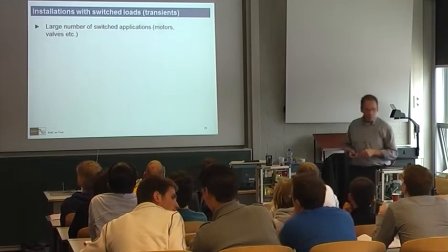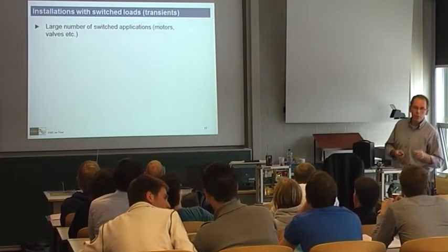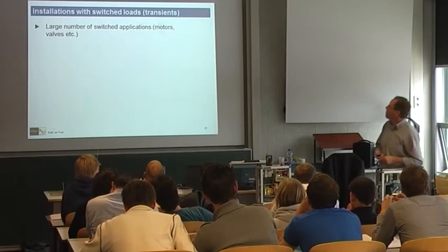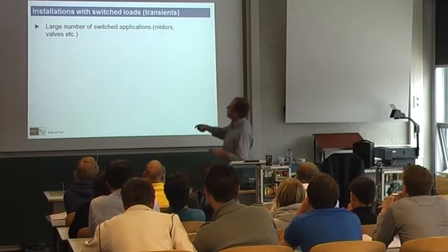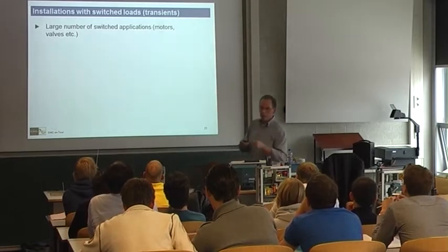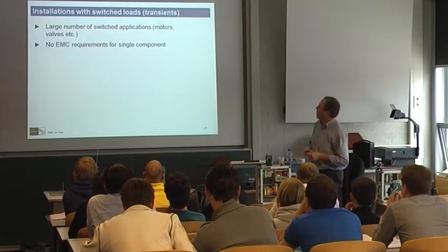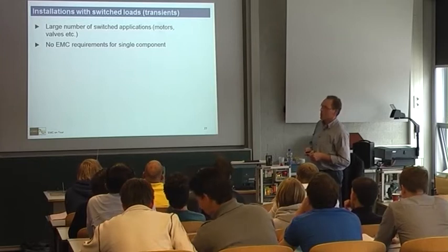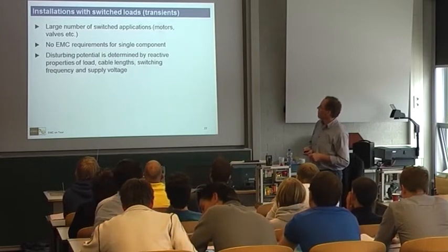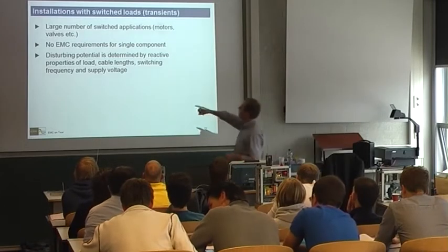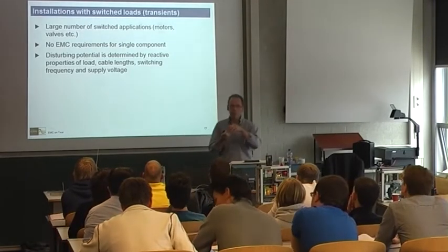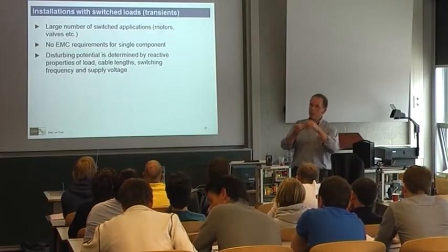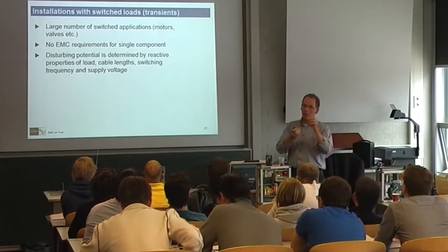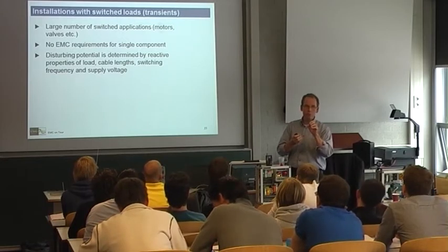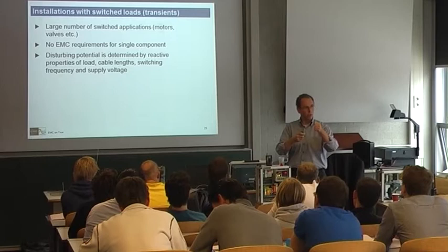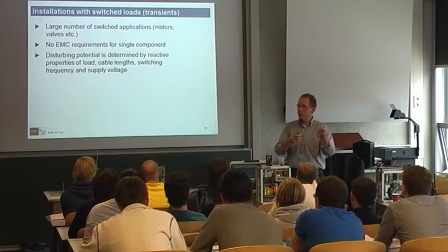Here's something about switched inductive charges, loads. You may have motors or valves switched on with the circuit breaker. There are no requirements in terms of standards because they're single components. But the point is they are reactive, so you've got stored inductive energy, and if you disconnect the current, you get a high voltage and sparking across the contacts. That's what you normally hear on the radio when a refrigerator switches off, you hear a click.